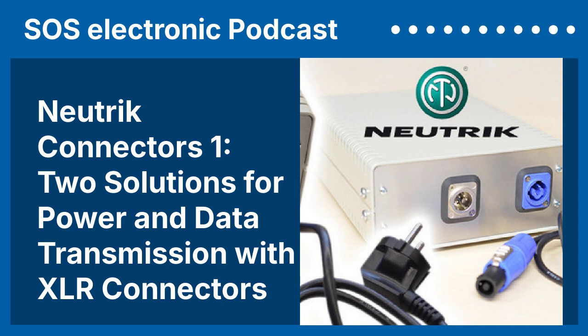A suitable solution could be, for example, a 4-core multi-pair cable 3082A T5U500 from Belden or 0030-937 from LAPP. For smaller currents, I can use a 4-core cable LIYCY 2x2x0.34 square millimeters with 2 twisted pair cables, which also comes from LAPP.